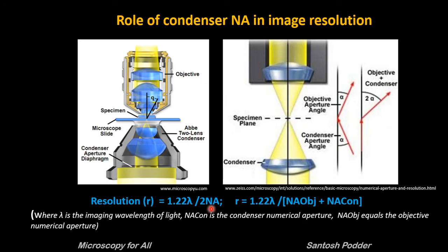Numerical aperture determines the resolving power of an objective, but the total resolution of the microscope system is also dependent upon the numerical aperture of the sub-stage condenser. Higher the numerical aperture of the total system, the better the resolution. The '2·NA' in the formula is actually the numerical aperture of the objective plus the numerical aperture of the condenser. The correct alignment of the microscope optical system and the adjustment of the condenser aperture are of paramount importance to ensure maximum resolution, as we learned during the setting up of color illumination in the last video.